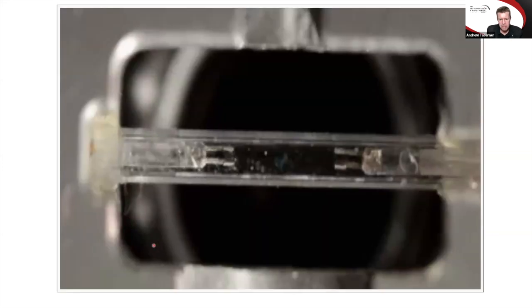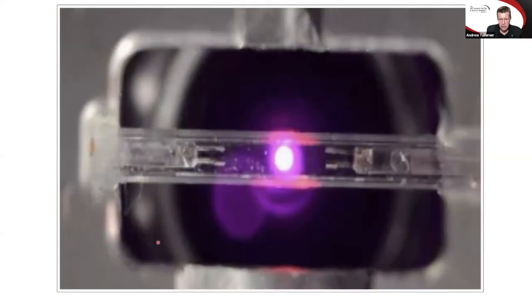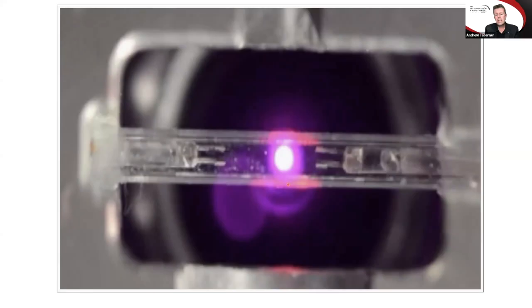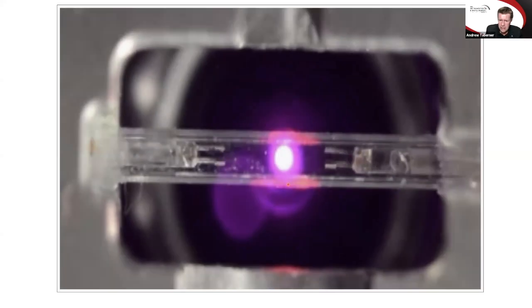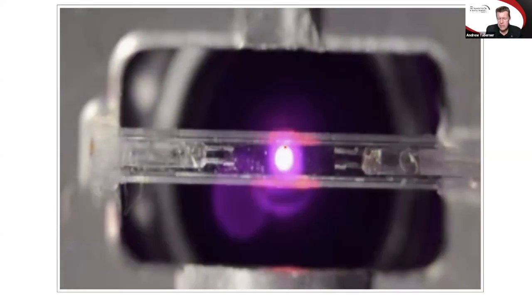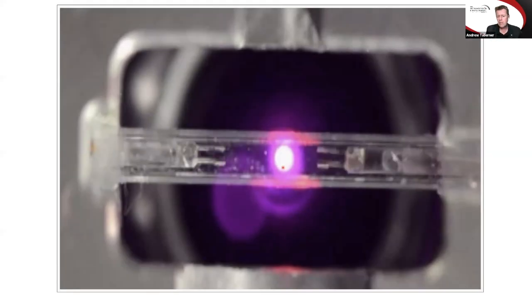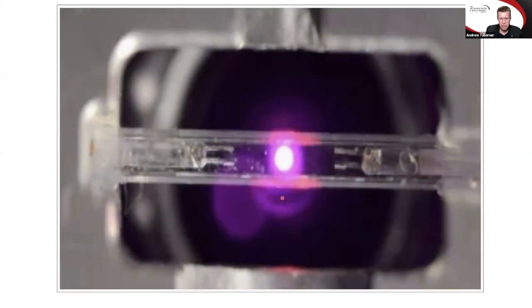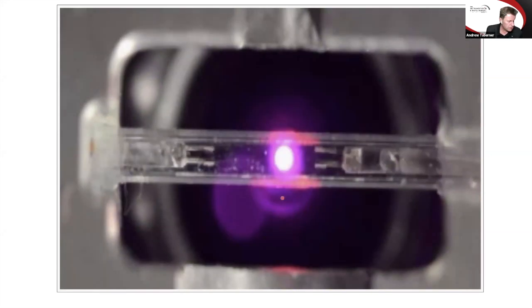If we look down on top of the instrument with a close-up view, here's our two hooks. We're looking down on top. And you can see here, we're just changing modes to show you that the motors that control either end of the muscle can now stretch, they can translate, they can contract. And in the center, these red lights and purple lights indicate the imaging system. The purple is the calcium imaging system, and we do white light microscopy also through the same system. And the OCT system is orthogonal in the direction of the red laser. The OCT, the optical coherence tomograph, gives us the three-dimensional shape.